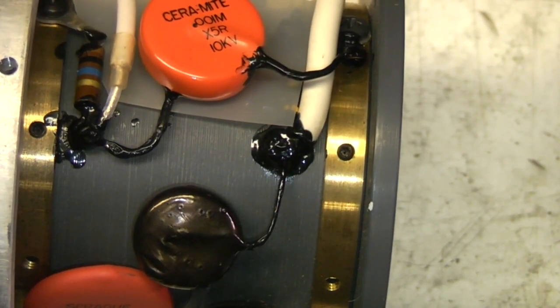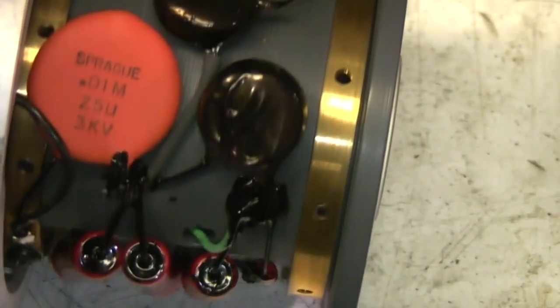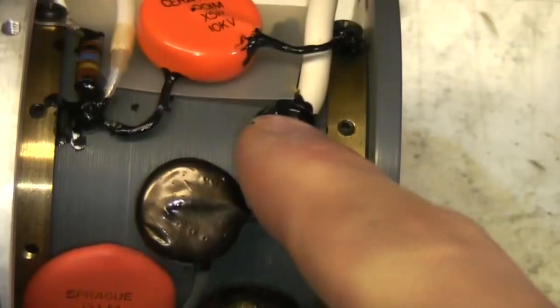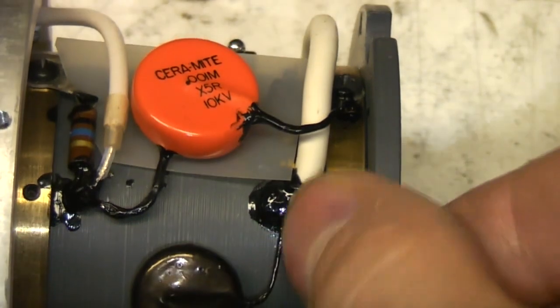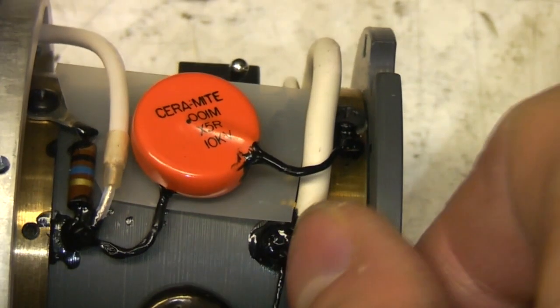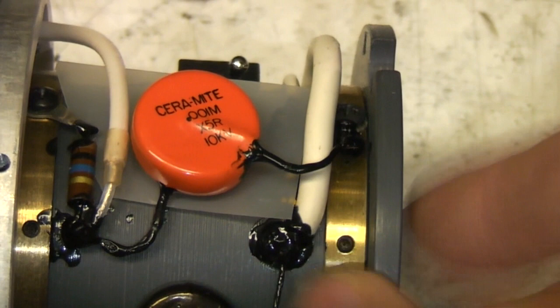One thing you'll notice, all these high voltage connections have got this black gunge on them. Now the reason for that is going to be to prevent corona. Wherever you've got an exposed high voltage connector, any slight sharp edges will produce corona losses, which produce ozone and all sorts of other nasties. So all this black stuff is just going to be anti-corona protection.